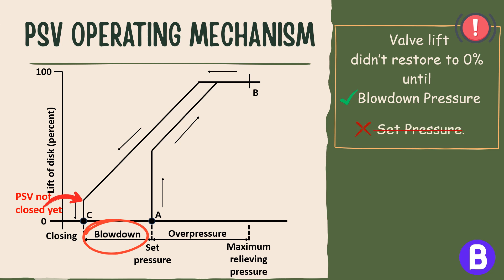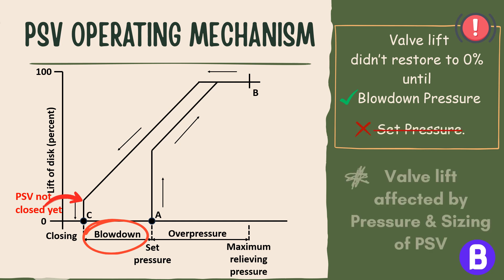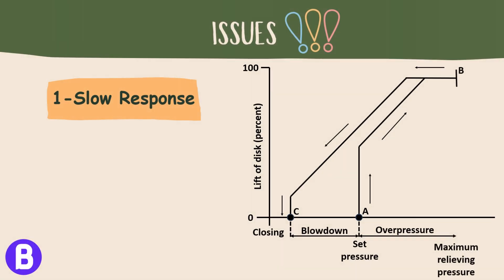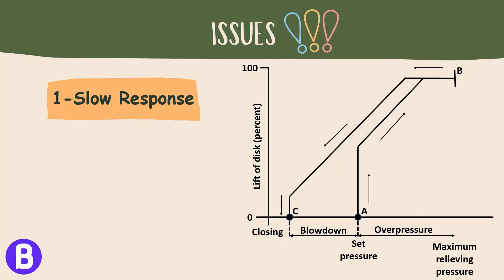This means that the valve lift percentage is highly affected by the current pressure at the pressure safety valve, which means that proper sizing of the pressure safety valve should consider the proper valve lift against the relief stages. Otherwise, this may lead to several issues.